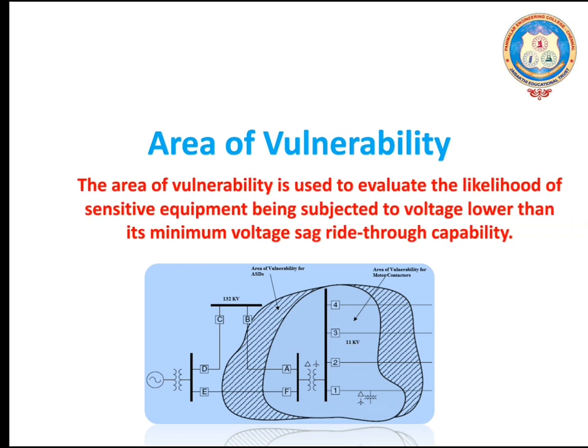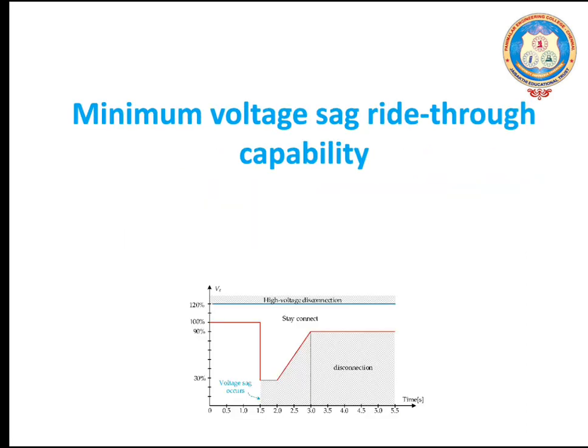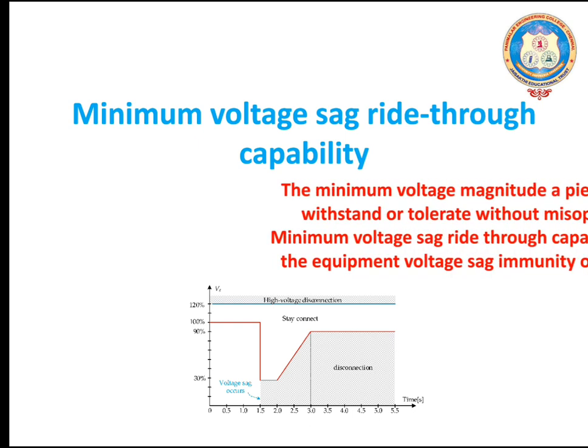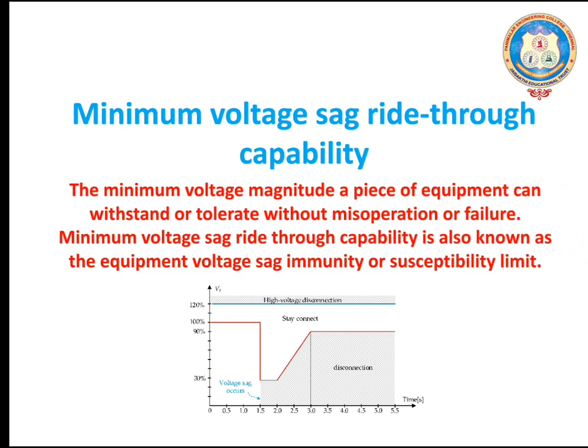The area of vulnerability is used to evaluate the likelihood of sensitive equipment being subjected to voltage lower than its minimum voltage sag ride-through capability. The minimum voltage magnitude a piece of equipment can withstand or tolerate without misoperation or failure is also known as equipment voltage sag immunity or susceptibility limit.